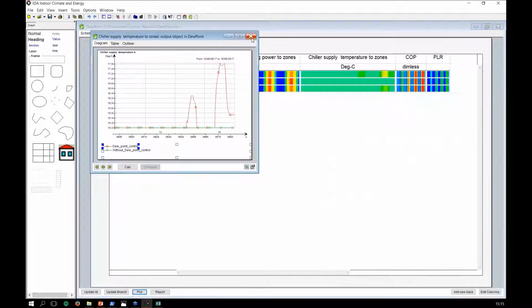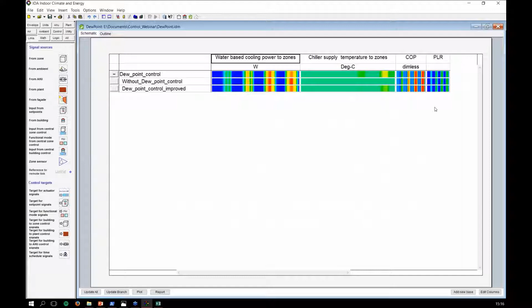How about the energy? Again, I'm going to remove this and zoom in. Well, you see when the dew point temperature is the same, they both consume the same amount of energy. But in the last 2 days, when the dew point temperature control kicks in, it goes from around 10,000 watts without dew point control to around 9,000 watts with the dew point temperature control. So that's 1,000 watt energy saving, just directly like that. So we're doing both energy saving and moisture control, condensation control.